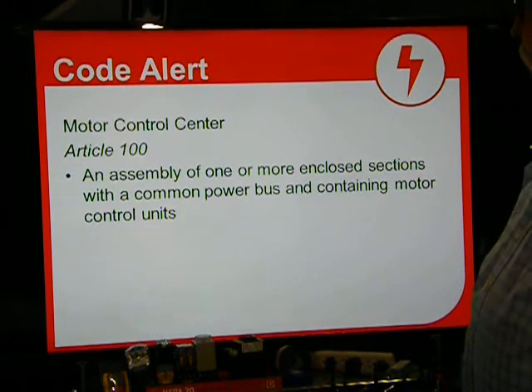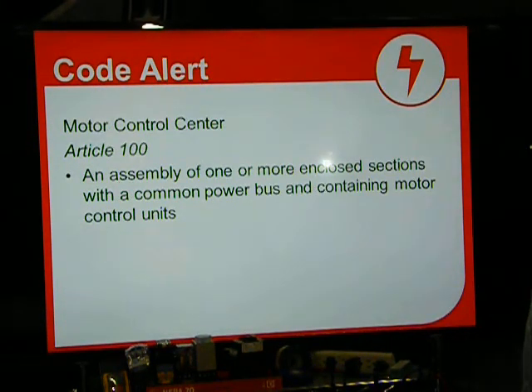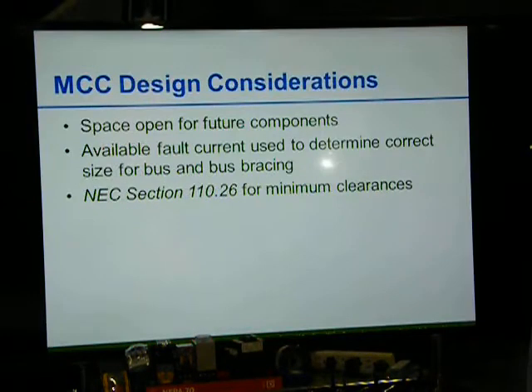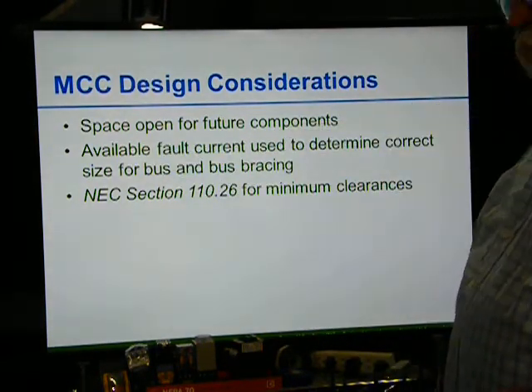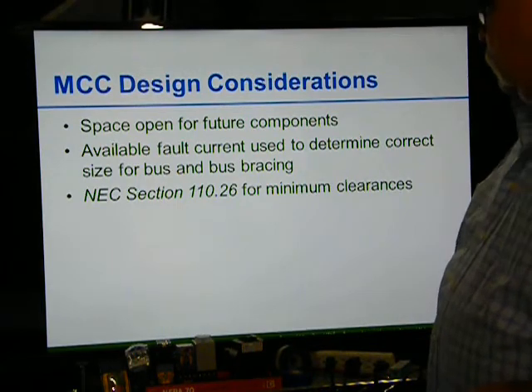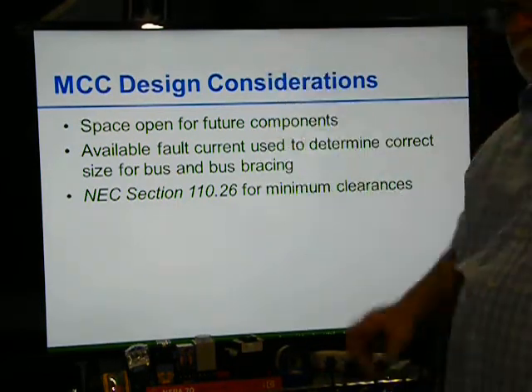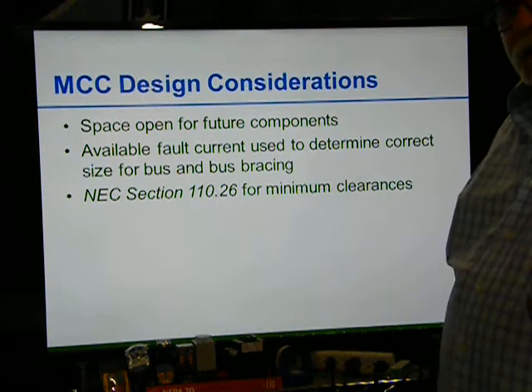Motor control center: an assembly of one or more enclosed sections with a common power bus containing motor control units. MCC design considerations. When you're designing one, leave space open for future components. The bus that's coming in there is all sized on the fault current.